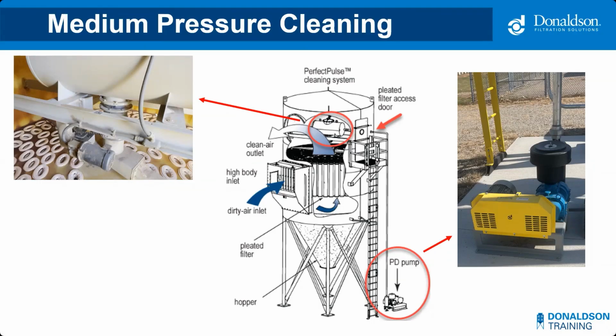It releases in medium volume pulses every 3 to 8 seconds. The timing of the pulses depends entirely on the arrangement of filters within the collector. Almost all of these collectors will have a logic built in so that the pulse occurs when they are directly over a number of filter bags to ensure the most effective cleaning.